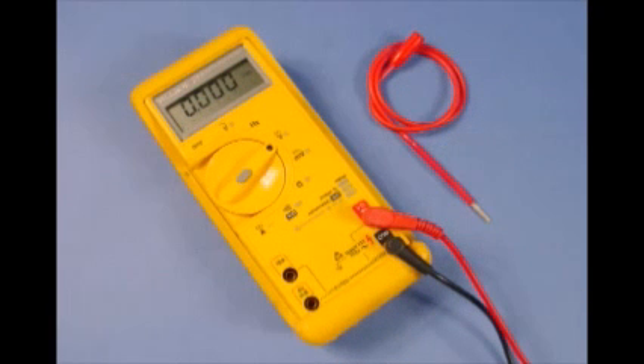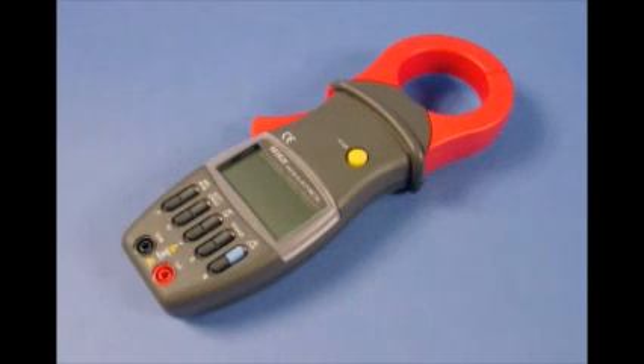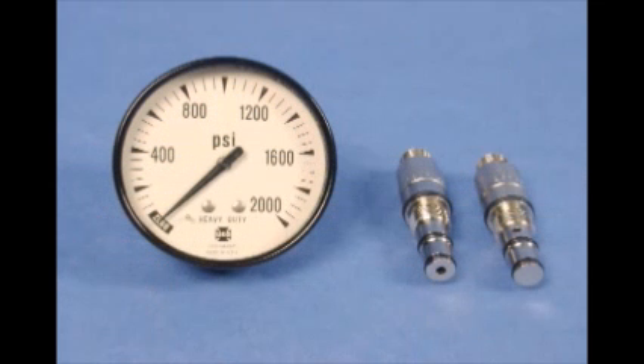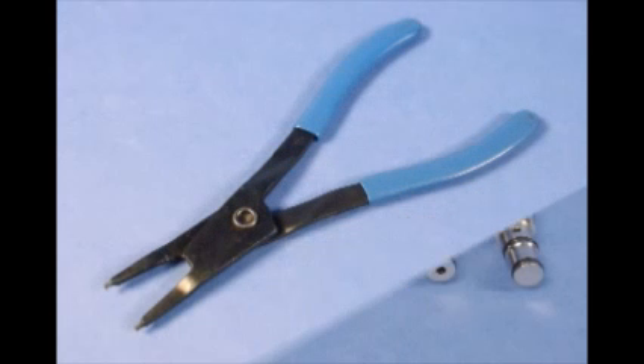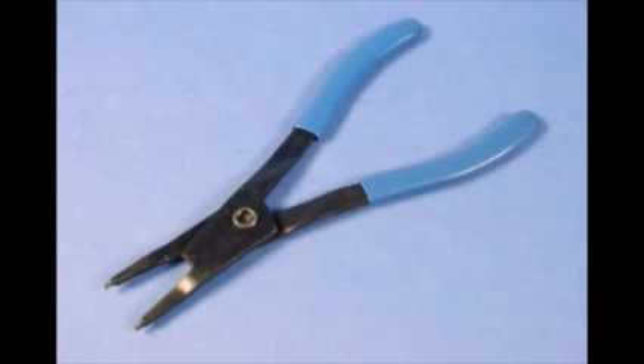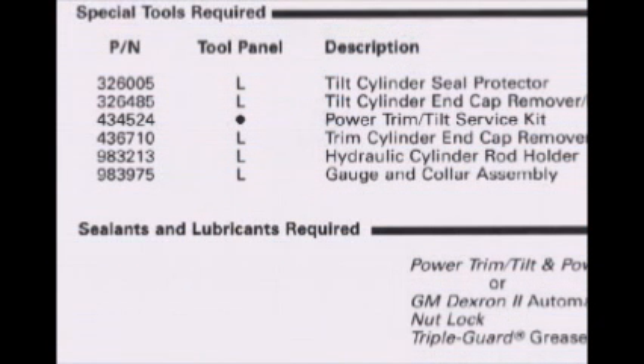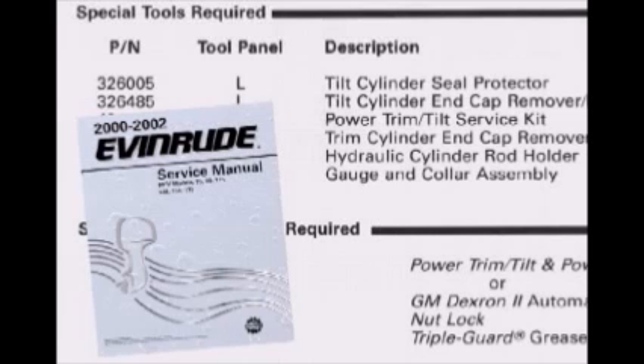When troubleshooting, you will need the following equipment: a volt-ohm meter for testing the electrical circuits, a DC ammeter capable of reading up to 100 amps for analyzing current requirements for the electric motor and hydraulic unit, a gauge and collar with adapters for checking hydraulic system pressure, and retaining ring pliers for removing the manual release valve retaining ring. A list of additional special tools for complete servicing can be found in the service manual.